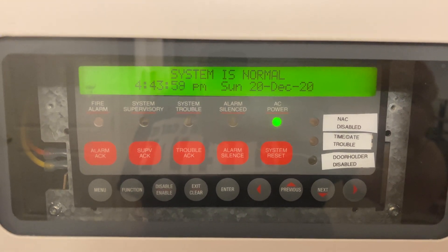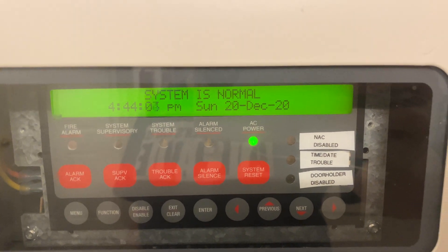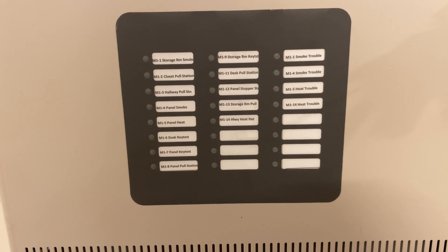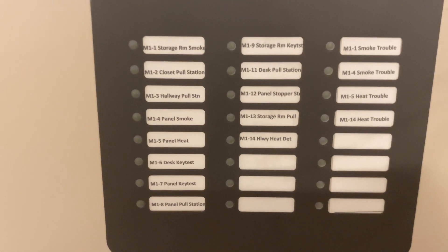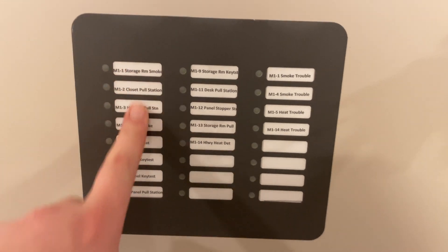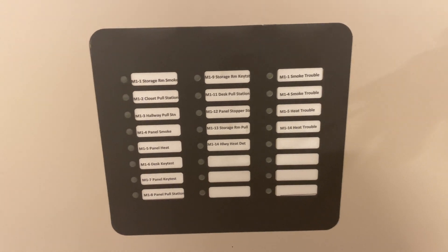Hey guys, welcome again to Fire Alarms and Such. This is Simplex 4010 test 34 — annunciator panel. There's a new 4010 here; as you can see it doesn't have that fire suppression label up there, and if you look down on the door there's actually a built-in 24IO card that can do point-by-point annunciation. You can actually see I have every one of my points listed here, including trouble points. You can switch these between red and amber LEDs, so I have alarm status for every single one of my points as well as trouble statuses for my smoke detector.